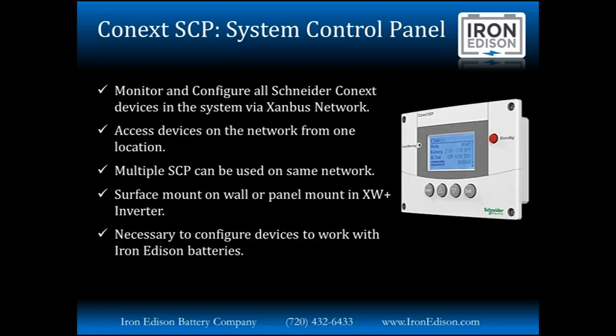The system control panel has a few mounting options. It can be surface mounted on the wall with the bezel that's included with it, or it's also designed to be panel mounted in the XW Plus inverter or the SW Power Distribution Panel. And with the advanced configuration and programming options, really the system control panel is a mandatory component when configuring the system to work with batteries like the Iron Edison battery.